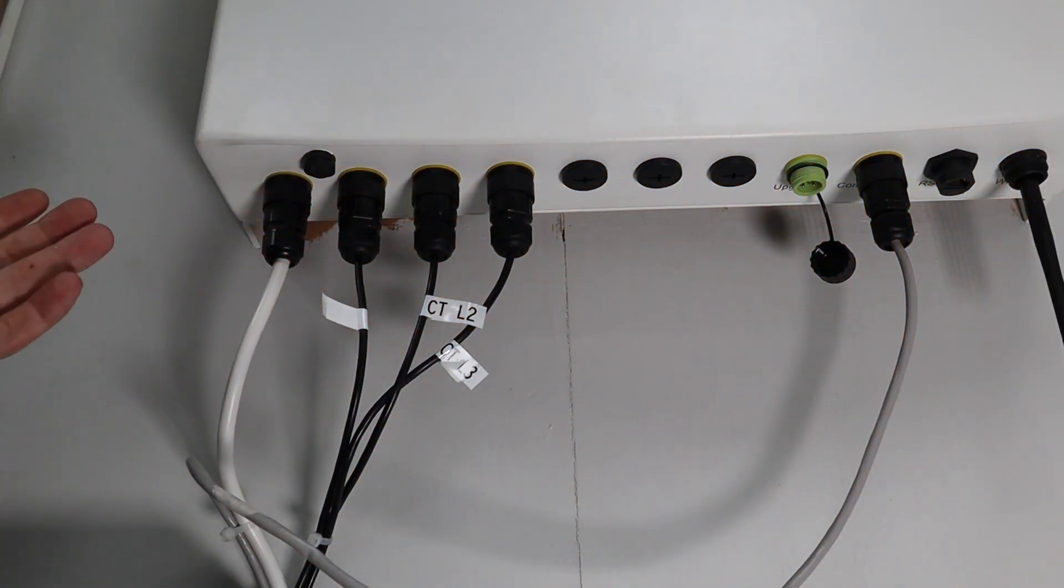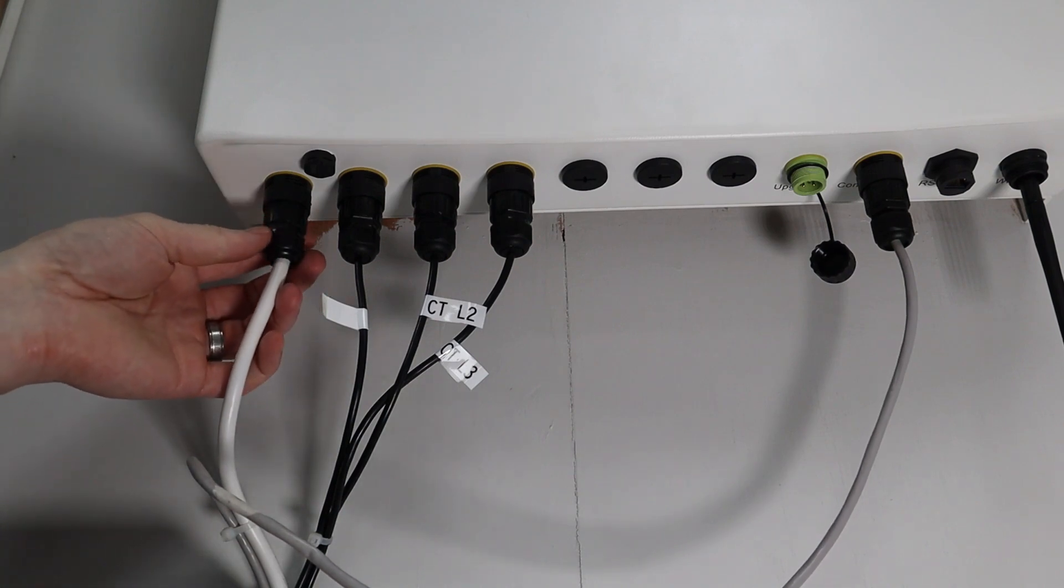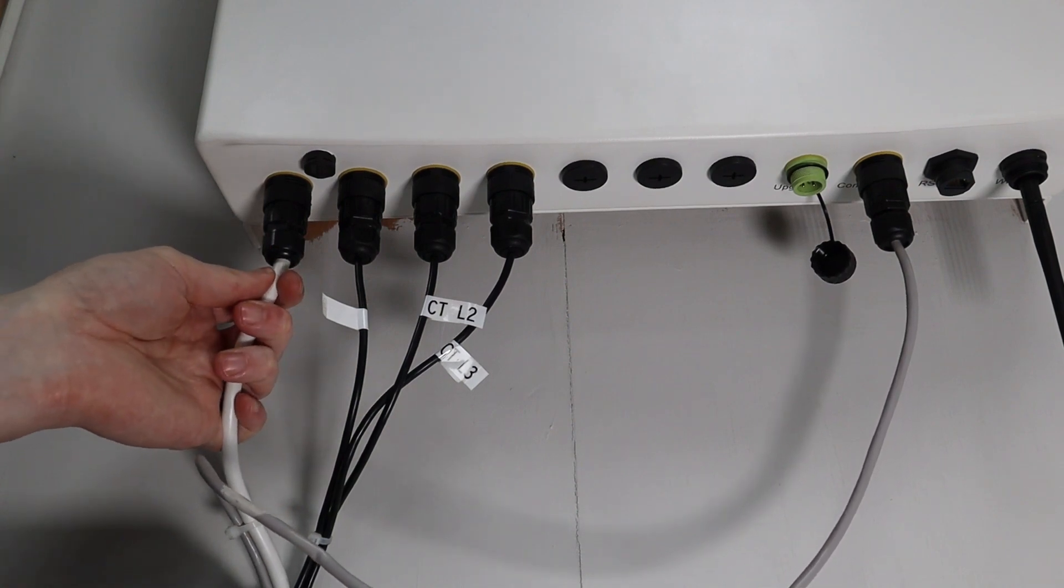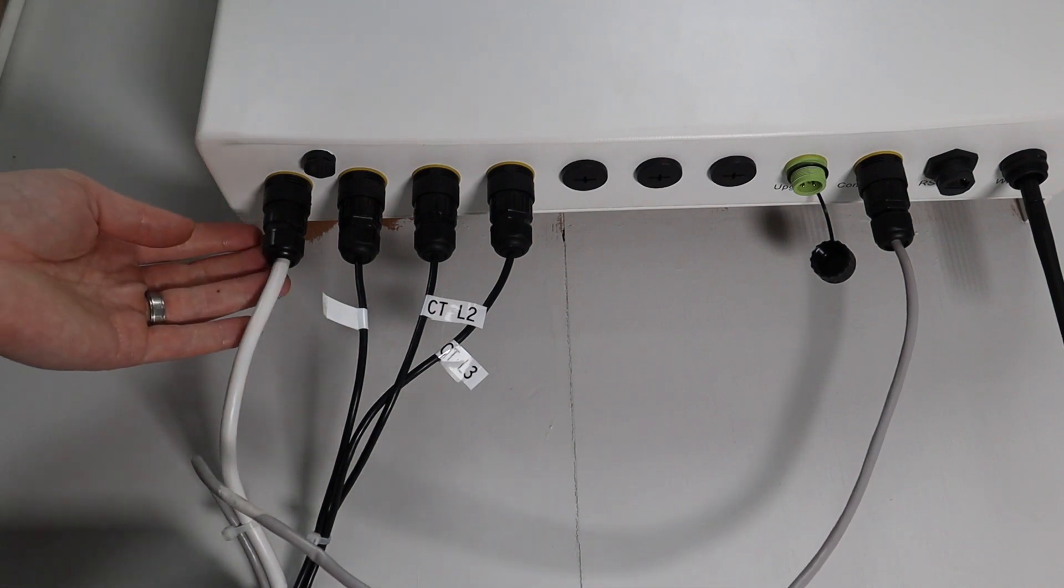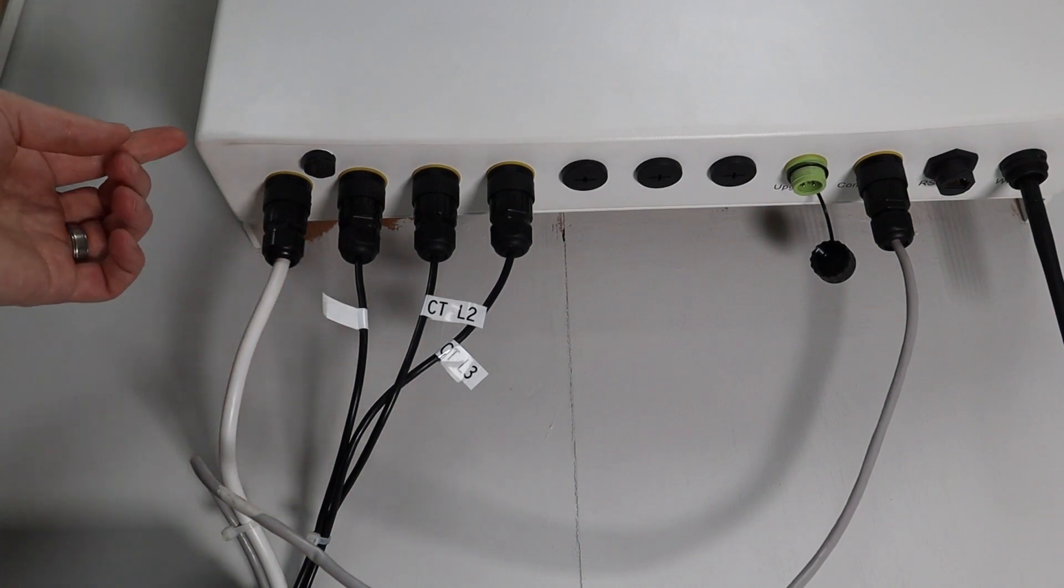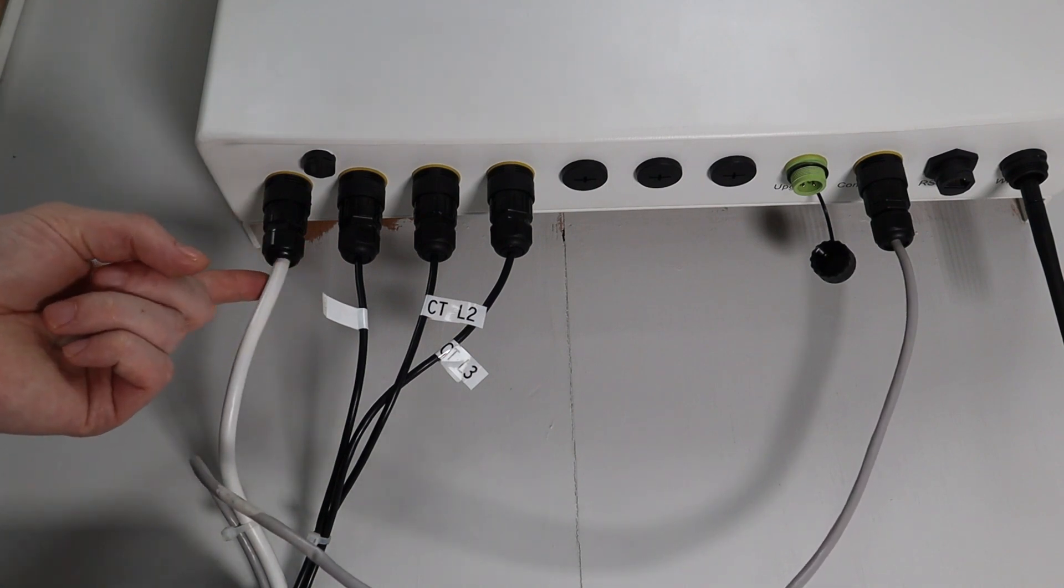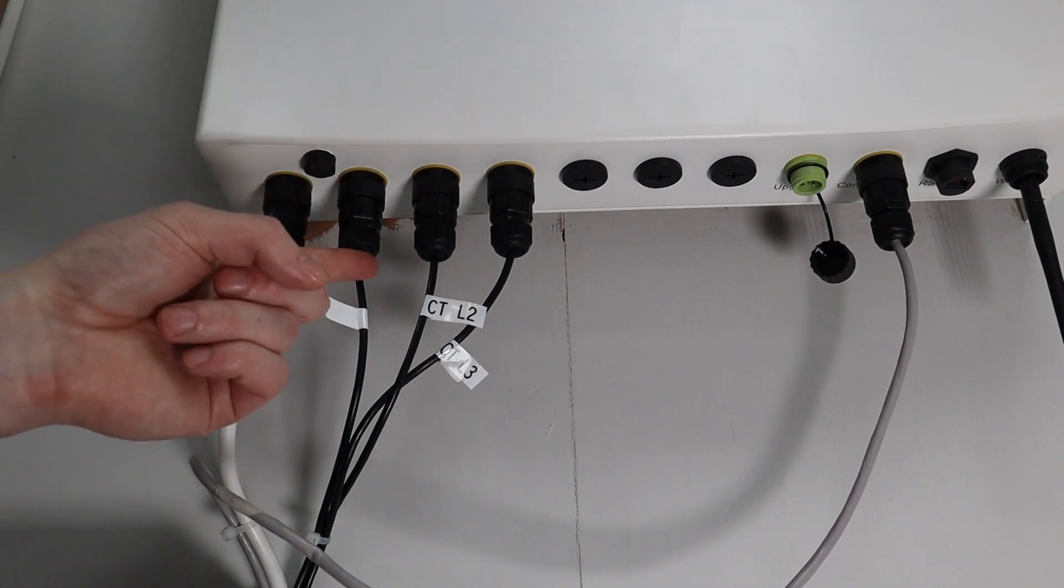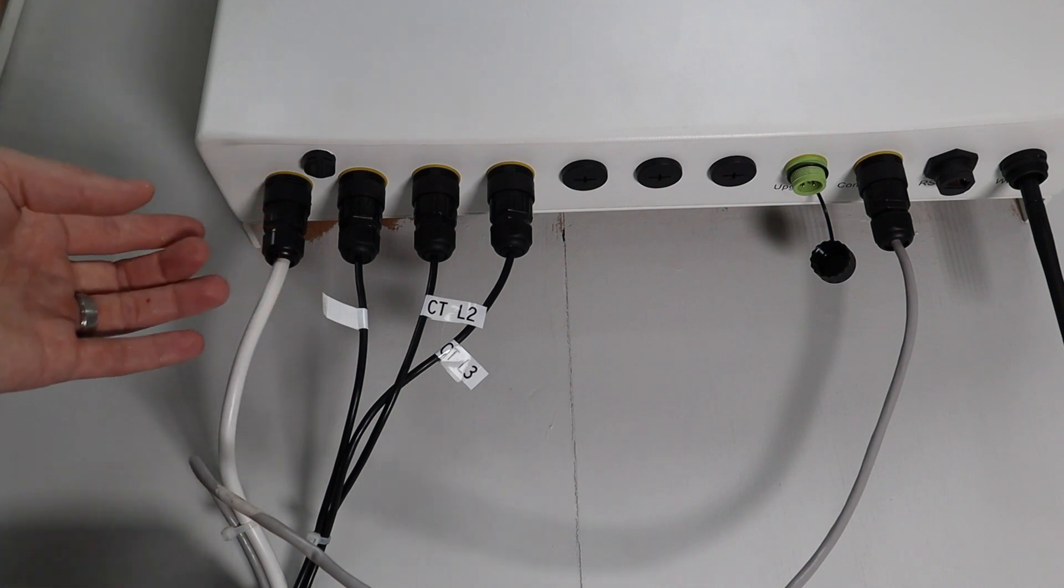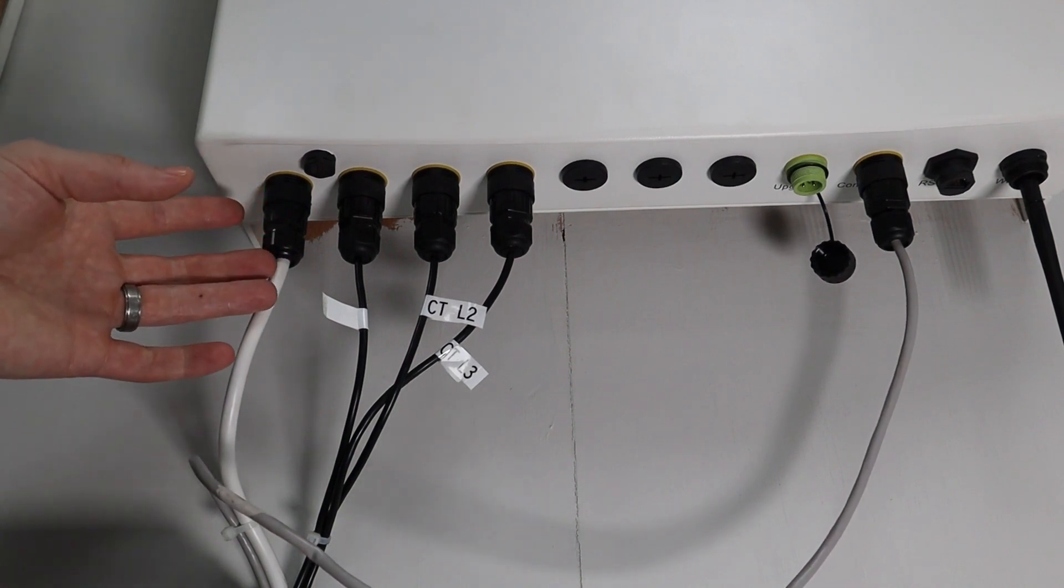Okay, so here we've got the bottom of the EPM. On the left-hand side, a very important plug is the voltage input plug for the EPM. It's got three phases in the case of the three phase models and it's got phase A, phase B and phase C, neutral and earth. It's very important that you get the phase rotation correct in this plug because if the voltages don't match, the CTs won't be able to match and you won't be getting correct real power values and the power factor will be wrong. So it's extremely important that you put phase one into the pin for phase one and two and three.